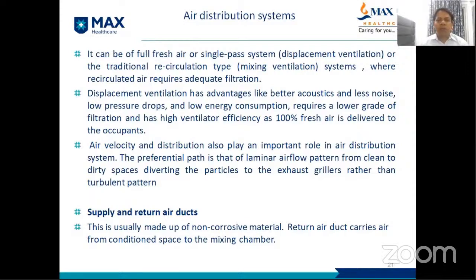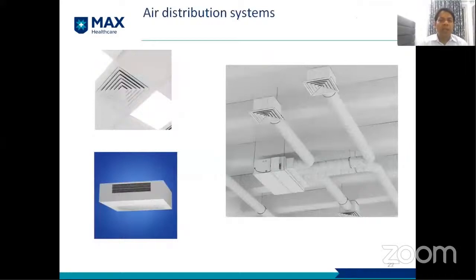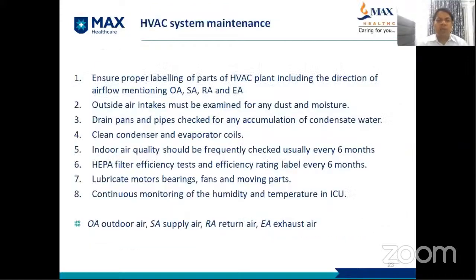Air velocity and distribution also play an important role in air distribution systems. The preferential path is a laminar airflow pattern from clean to dirty spaces, diverting particles to the exhaust grill rather than creating turbulence patterns. Supply and return air ducts are usually made of non-corrosive materials. Return air ducts carry air from the conditioned space to the mixing chamber. These are some of the air distribution systems, ventilator systems, and FCU.